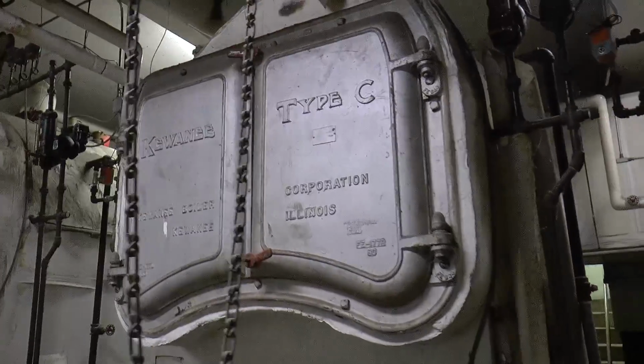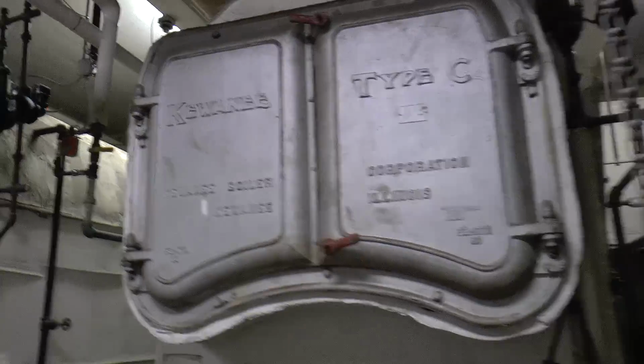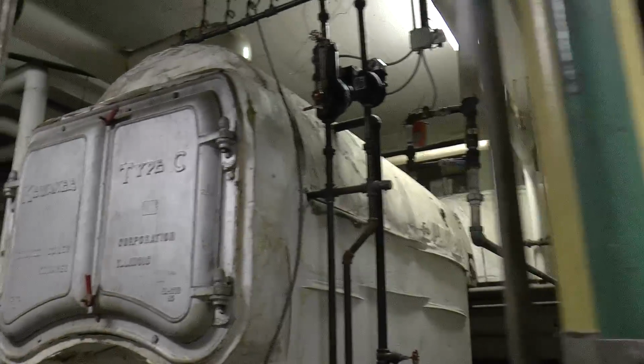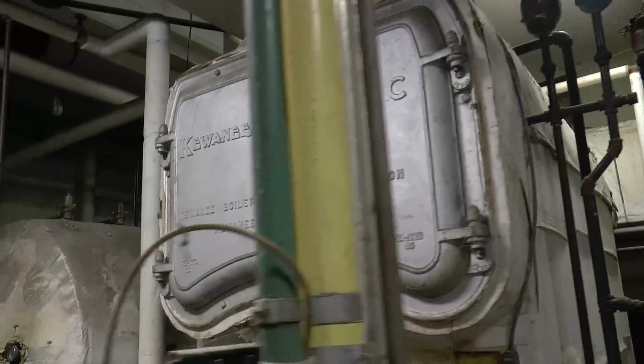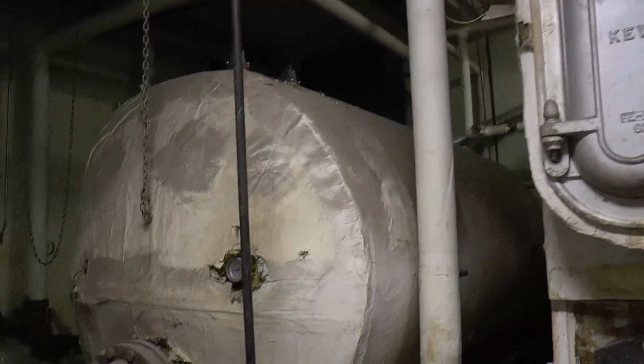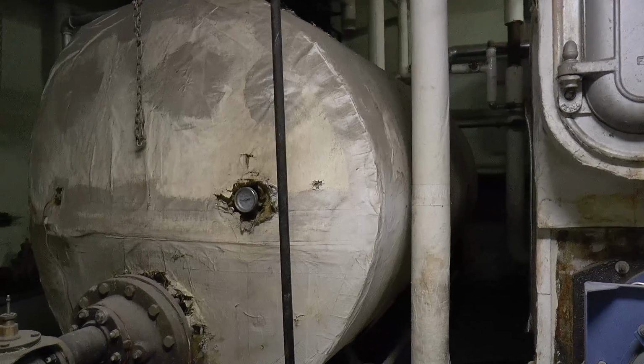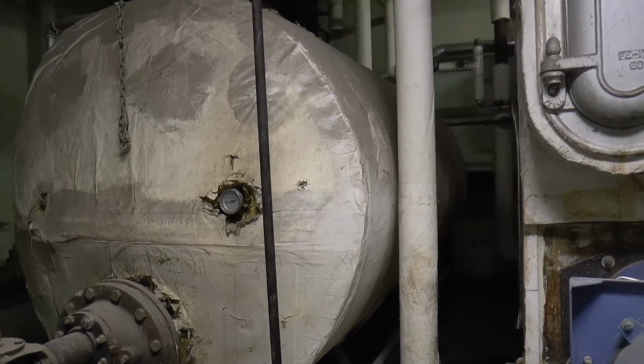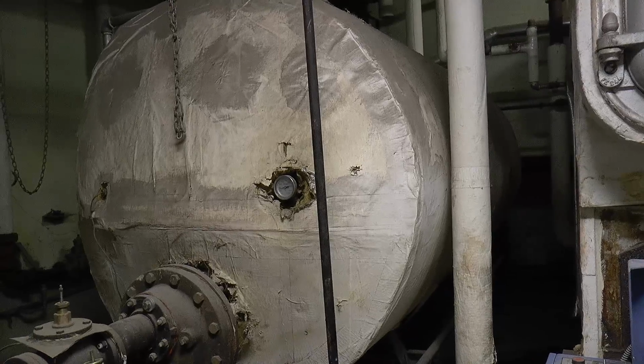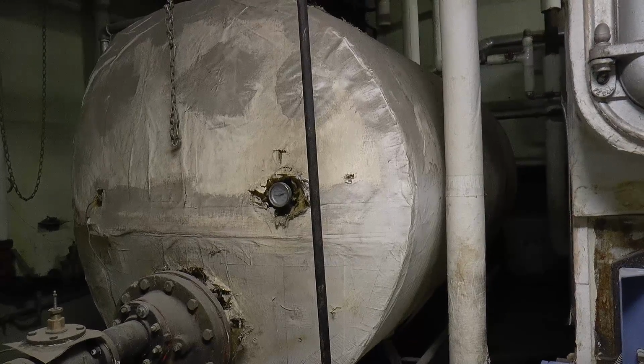They're also very highly inefficient because the unit ventilators that regulate the heat don't work. So the way we heat the building is the custodians come down here and turn the boilers on or off. There is no automatic turn on or off or thermostat regulation. It's just basically running.